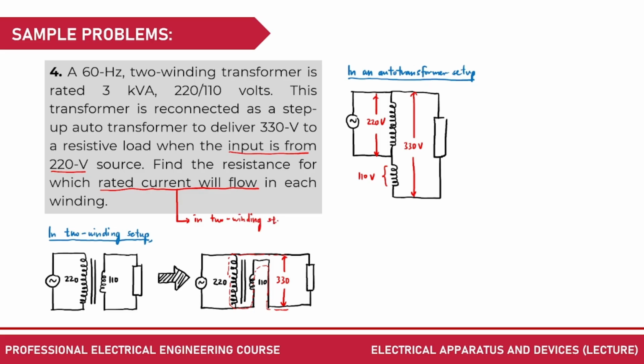I'll explain. When you design a transformer, let's say it's two-winding, the conductors used there were designed depending on the ampacity, based on your load, correct? Let's say you have a load, you get the rated current, so you choose a conductor. Once you choose a conductor, that's it - it has a rated current from that. When you convert it to an autotransformer, the rated current still needs to continue to be delivered; it shouldn't go up or down, it needs to stay the same.